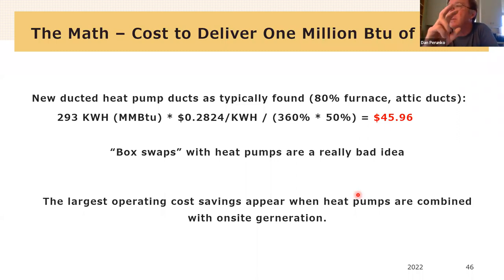If you do what's called a box swap, where you take the, they call them boxes, right? Because the furnace is a long rectangular box and the evaporator coil is like a little cube. If you take those two boxes out and you put heat pump boxes in place of them, but you don't make any of the duct improvements, and you go back to this math, you've got your 360% equipment efficiency, but you still have 50% duct losses and you have an expensive fuel, electricity is expensive. So you end up with your cost per million BTUs at $45.